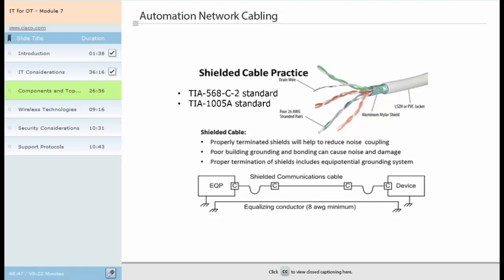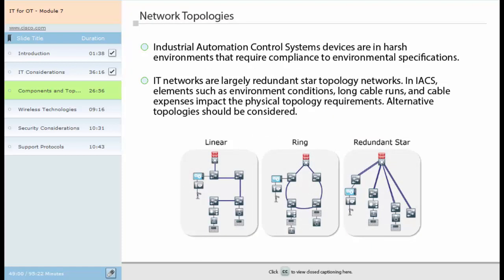Industrial automation control system devices and network infrastructure often include long cable runs in potentially non-controlled conditions such as humidity, varying temperatures and noise vibrations. These challenges are what IACS networks face that typical enterprise networks do not. Network design should take into consideration compliance regulations and potential environmental hazards. Elements such as harsh environmental conditions, long cable runs and expensive cable determine how the network topology for IACS networks is designed. Unlike IT networks, which often form redundant star topology networks, IACS network formations are driven by physical requirements such as the series of interconnected motion devices of an assembly line. Alternative topologies such as linear, ring and star need to be considered.